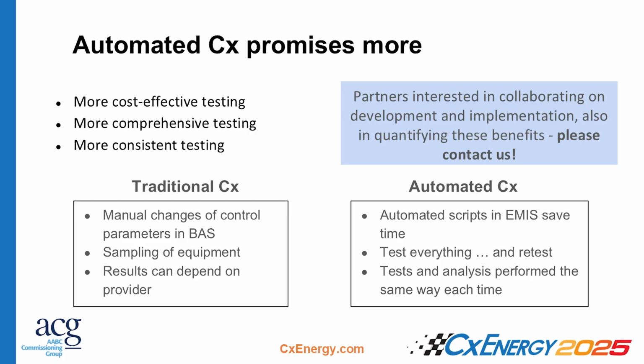There's this whole 10 to 20% sampling standard for VAV boxes. You may do it physically, but with automated commissioning, you can get 100% of the boxes all of a sudden, right? This is a really funny one too, but there's the mundaneness factor, right? If you're having a commissioning agent going out and commissioning 125 VAVs, by the 50th VAV, they're nodding off and falling asleep. Number one, they're tired, they don't want to do it. Number two, they're more prone to mistakes if they're dozing off. Doing this in an automated fashion allows you to have more consistent testing, more comprehensive testing, and then in some cases, through follow-up testing, you actually get more targeted responses in terms of the underlying faults that could be causing the failed testing.